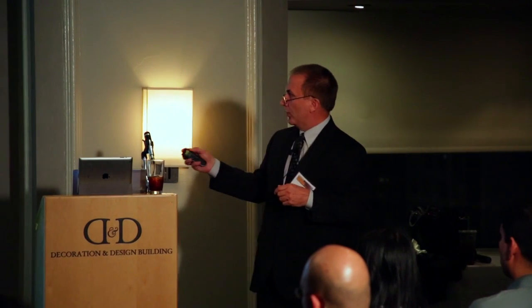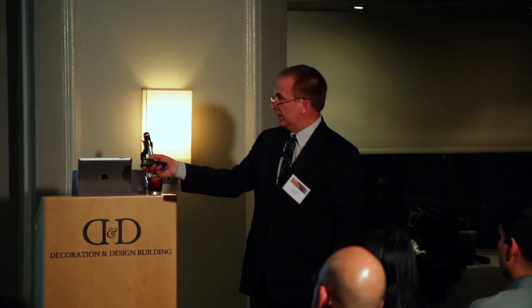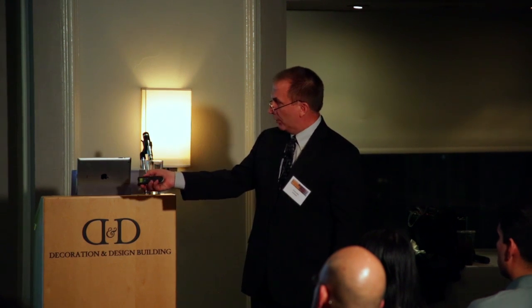When we analyzed one of the labs at Princeton using their 12 air changes per hour, what we noticed in the initial design — blue is air moving slow, red is air moving very quickly — is that we were actually moving the air so rapidly that we were creating vortexes and eddies as the air came around some of the fixed equipment in the room. So instead of evacuating the fumes, we were actually holding the fumes in those eddies.